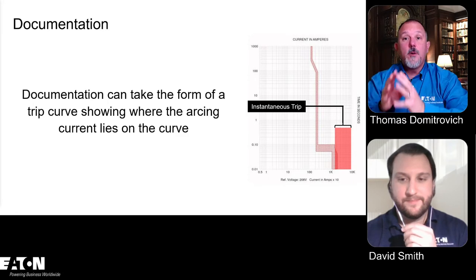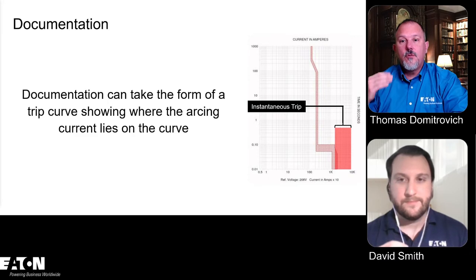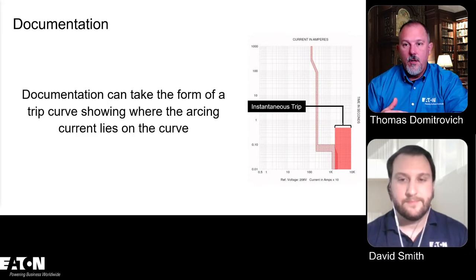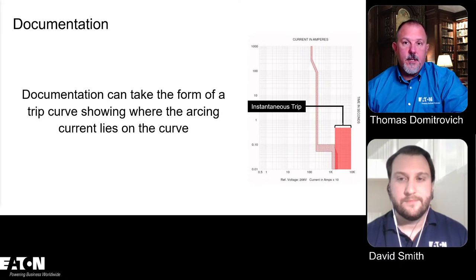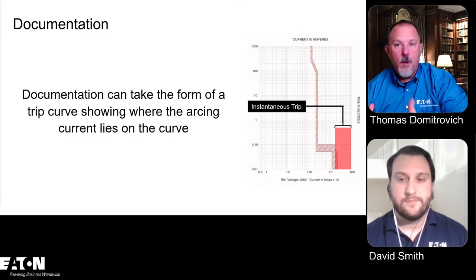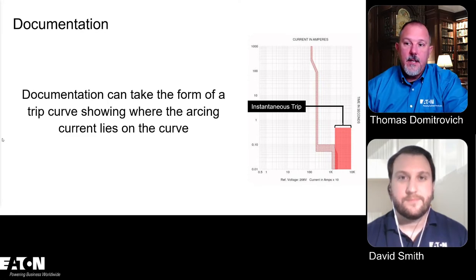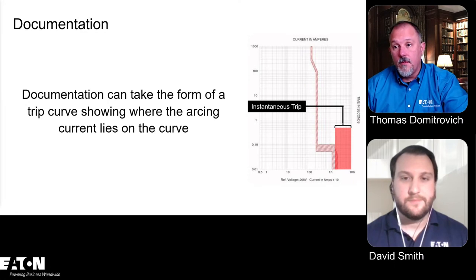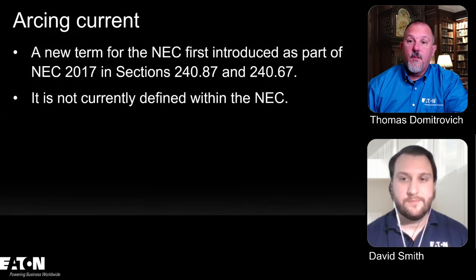So the instantaneous region, it's important to understand what the instantaneous region is on a trip curve, right? So for documentation, you have to show that your arcing current is either in the instantaneous region or in the activation zone for one of those technologies. And if you're using instantaneous, it's important to understand what is instantaneous and how to read the trip curve. So very critical for proper application.